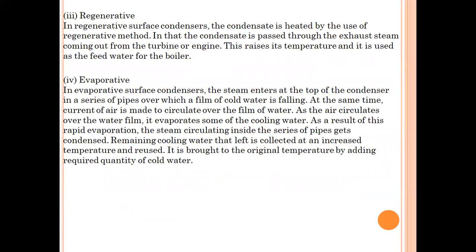Regenerative condenser. In a regenerative surface condenser, the condensate is heated by the use of the regenerative method. In that, the condensate is passed through the exhaust steam coming out from the turbine or engine. This raises its temperature and it is used as the feed water for the boiler.